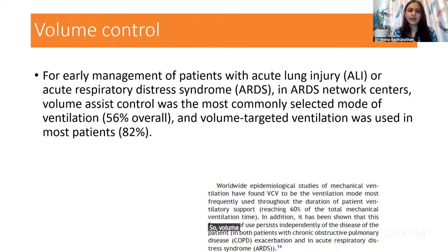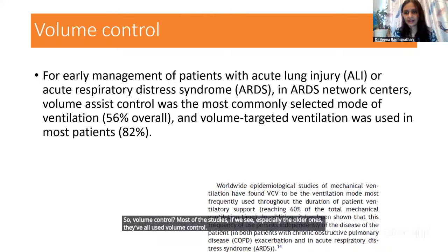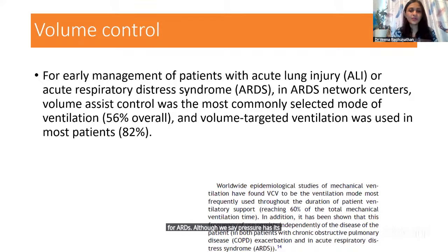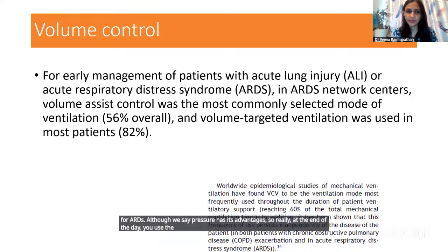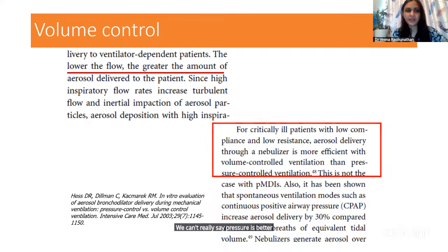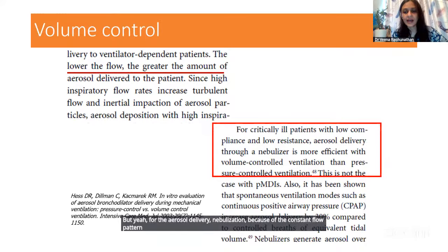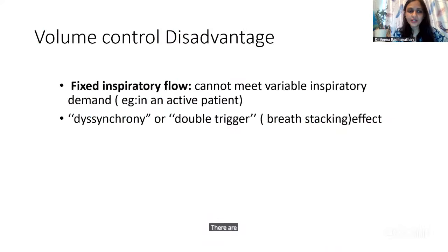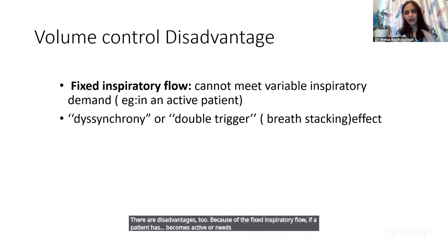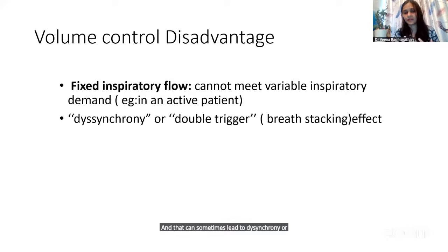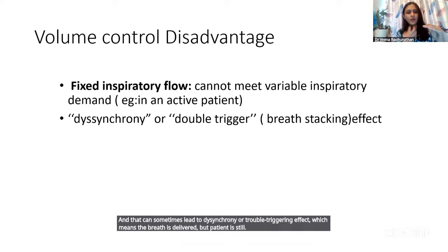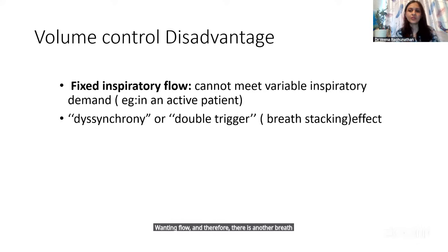So volume control, most of the studies, especially the older ones, have all used volume control for ARDS. Although we say pressure has its advantages, at the end of the day, you use the mode which you are comfortable with. We can't really say pressure is better or volume is better. But for aerosol delivery, nebulization, because of the constant flow pattern, volume control has some advantage. There are disadvantages too. Because of the fixed inspiratory flow, if a patient becomes active or needs a higher inspiratory flow, this cannot meet that demand. And that can sometimes lead to dysynchrony or double triggering effect, which means the breath is delivered, but the patient is still wanting flow. And therefore, there is another breath which comes on top of this, which is called the breath stacking effect.